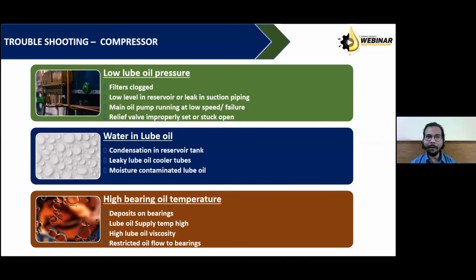This is directly related to contamination, because the relief valve of a compressor lubrication system has a very small seating area and a very small ball, maybe having a diameter of 4 mm or less. So any small micronic particle, maybe a 15 micron or 20 micron particle, has a tendency to lift the ball from the seat, and then the function of the relief valve will go off.